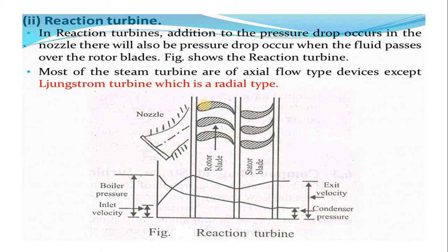These are the moving blades, another name for which is rotor blades, where the velocity energy gets absorbed by the blade and it starts rotating. Next the steam enters onto the surface of the stator blade. It is fixed to the casing and is called the fixed blade. It performs the same function as the nozzle. Here you can see that the velocity goes on increasing when the steam comes in contact with the stator blade, by reducing the pressure.